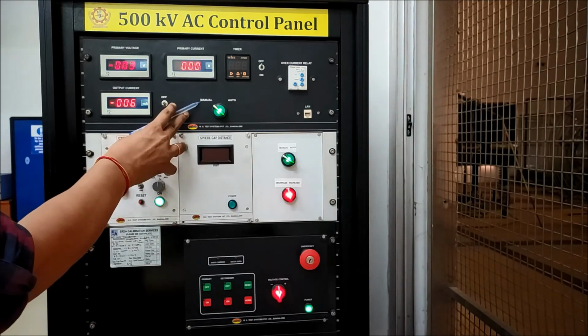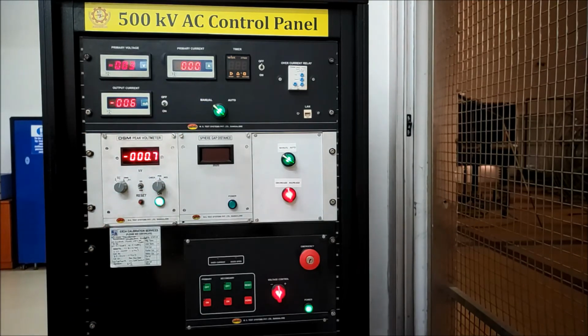Okay, this is the manual mode and auto mode. I have already set it in manual mode because I operate the control panel manually. And this indication is overcurrent. If any short circuit appears, the current will be very high. Then the indication shows here, and at that time you cannot start your experiment. First solve the problem and reset the overcurrent, then you can start your experiment. First switch on the primary, then the secondary. And this voltage is measured in kV and RMS value.